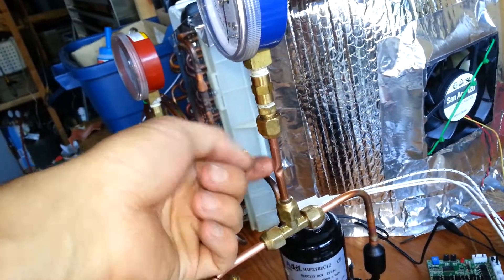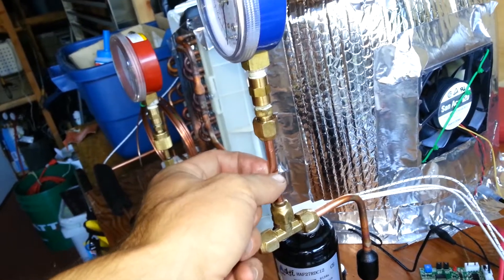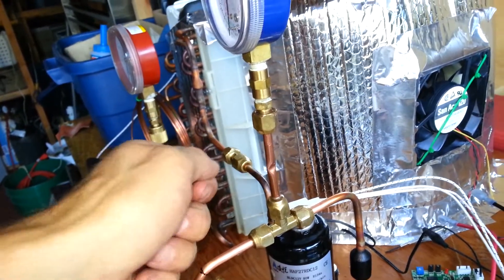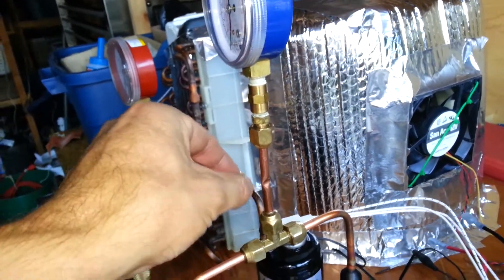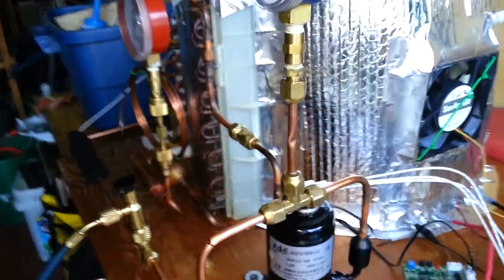I put a copper line in here and I pinched it so it's just barely cracked, like a service valve crack. So hopefully that'll take care of some of my flutter. If I have to, I'll pinch it a little more, but I think it's probably going to make a huge difference right there.